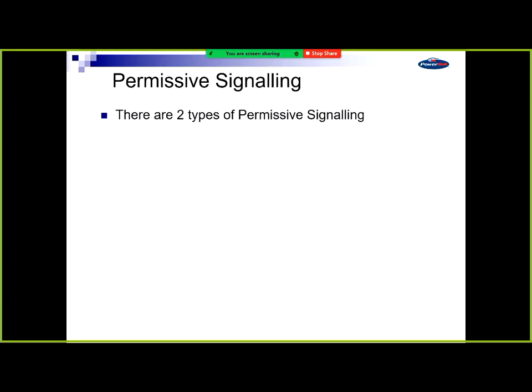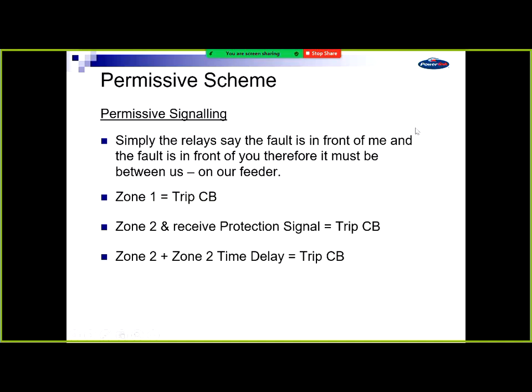So we term it, if it's just a zone 2 operation, the terminology we use is slow zone 2. You see it's not written there, but that bottom one being a zone 2 and the zone 2 time delay we term slow zone 2. The middle one, where you get a zone 2 and a protection signal to get you to go quicker, we call a fast zone 2. That's just the terminology that we use. So both of them are a zone 2 operation, but one's just faster than the other.